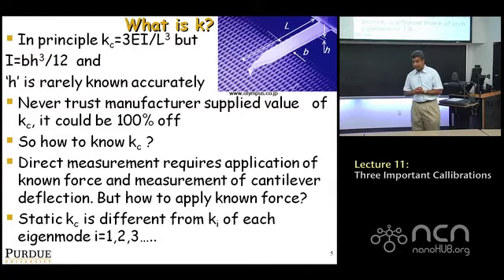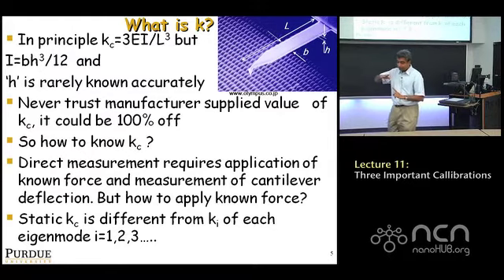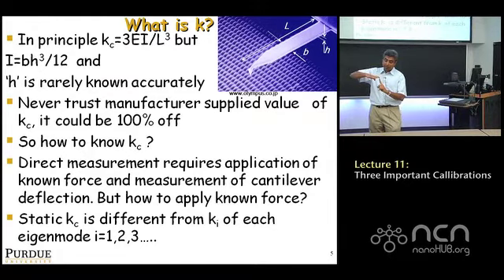The other thing to keep in mind is that there is a difference between measuring the stiffness when you apply a point force and the cantilever just gently bends, and the stiffness of an eigenmode of a cantilever. Because when you're doing dynamic AFM, remember, the shape in which it oscillates is a little different. It's not this nice cubic curve you get. And so the bending and the strain energy associated with a cantilever oscillating in an eigenmode is different from that of a point force. And so the stiffness, i.e. the spring constant, clearly depends on the shape in which it bends, and the shape in which it bends depends on the eigenmode.